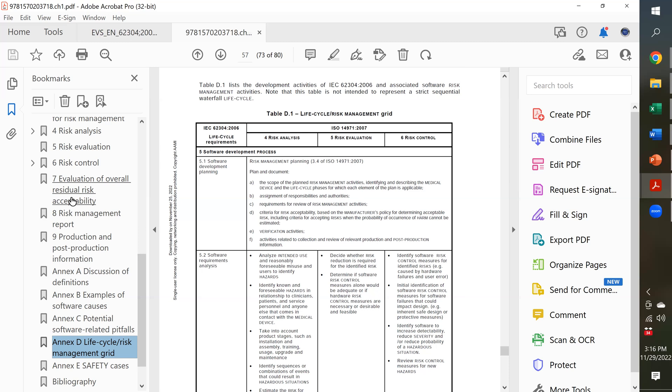It's not what people expect for an FMEA. Whereas if you have a fault tree analysis, it actually is more useful for how you're actually going to use your risk analysis in the future, and it kind of lends itself to making sure, do we have traceability in this module for each of the possible things that can go wrong, all the hazards, up to what is this section of the software supposed to do? And you could even have each fault tree dedicated to a different module, and based on the importance of that module and the hazards associated with that module, you could determine this module is higher priority, higher risk than the others, and we need to put more time into verification that the risk controls are adequate. Whereas another module might be less critical, and you can compartmentalize some of your risk controls and risk verification activities based upon the hazards presented or severity of hazards presented for that particular module.